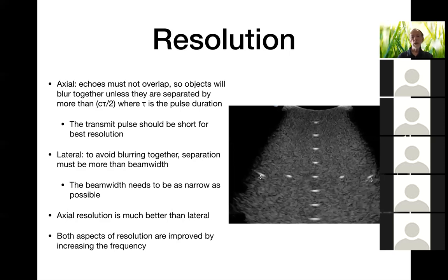This is actually an image of an ultrasound test target, or phantom, and it contains soft tissue type material, which we're not interested in at this point, but it has a whole series of targets. These targets are very thin nylon lines, less than a millimeter in diameter, and they go perpendicular to the scan plane. So the machine should be scanning them in cross section, and they should ideally look like little white dots in the image.